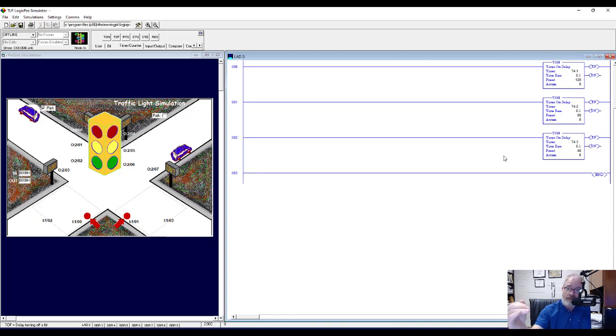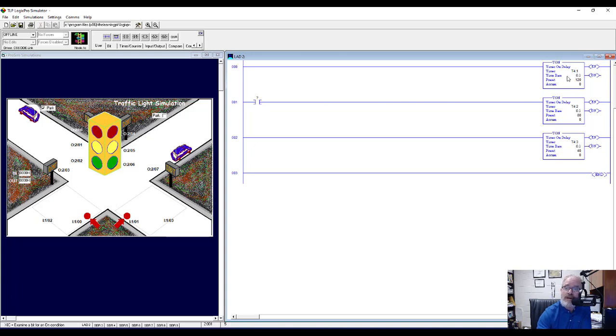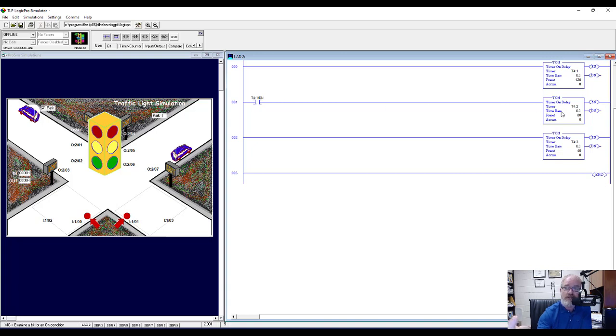We want one timer to time first, then start the next. So we're going to grab an examine-if-closed instruction and put it on the second rung with the second timer. We want the first timer, when it's done, to start the second timer. So we put in T4:1/DN — the done bit. When the first timer goes done, this instruction becomes true and energizes the second timer; it can't start until the first timer has finished.